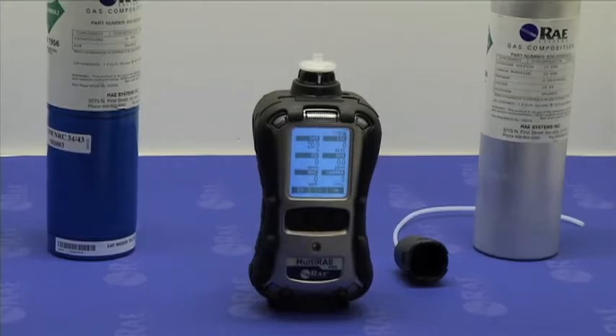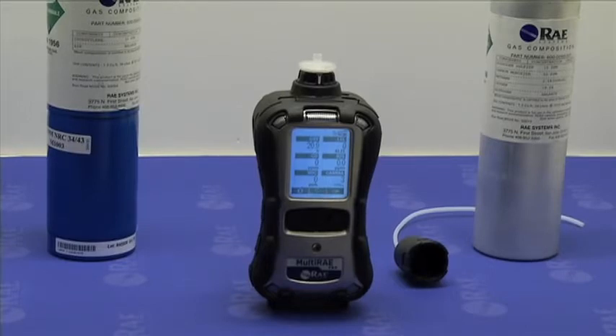The MultiRAE can be manually calibrated in two ways. One, you can calibrate individual sensors one by one, or, depending upon the configuration of your particular MultiRAE and the span gas that you have in possession, you may be able to calibrate multiple sensors at the same time.